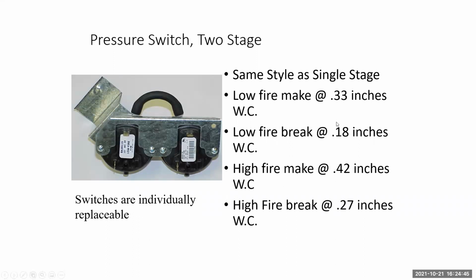Also, for the newer techs just getting into the heating side, your inducer has to provide at least time and a half or more in order for your switches to close. So just keep that in mind. Have a little 1/4-inch T and an extra piece of vinyl hose with you so you can tap into your inducer line and check your pressure going to your switches so you can determine whether it's a switch problem or a motor problem or a clogged flue problem or clogged secondary, whatever your problem. Make sure you have the right tools to do the right jobs.